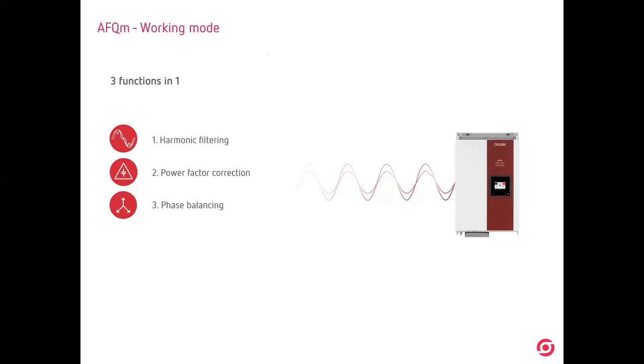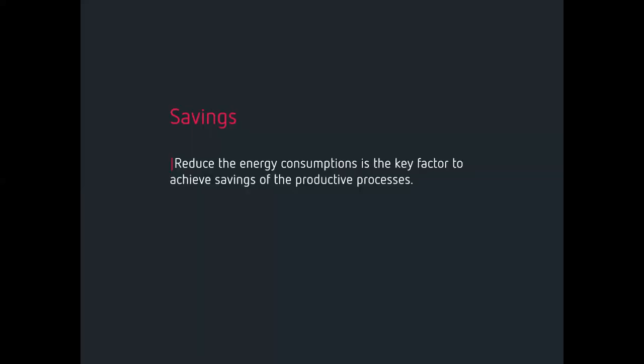By balancing the phases, what you will do is avoid or reduce this neutral current and reduce the problems that this neutral current can create. Okay. So an active filter is not just used for filtering. If we have more power, it will be used for improving the efficiency of the installation. Okay. Now, savings, the third point, okay?